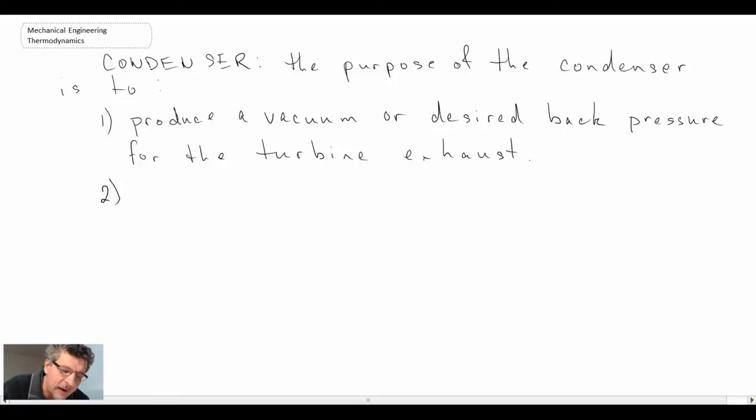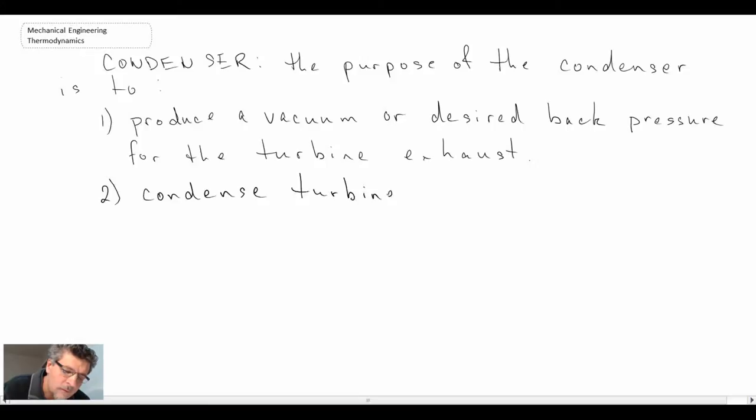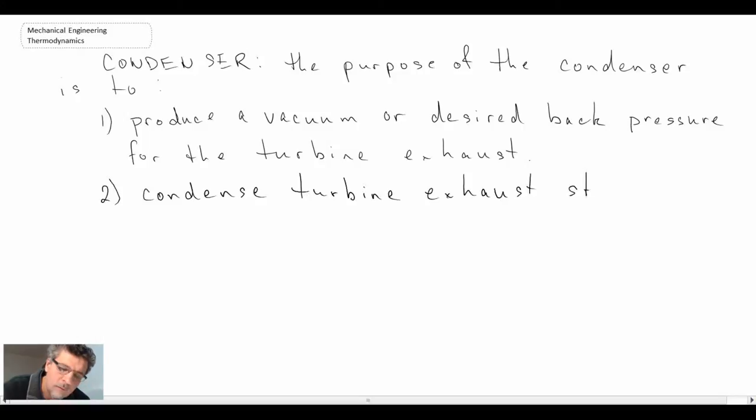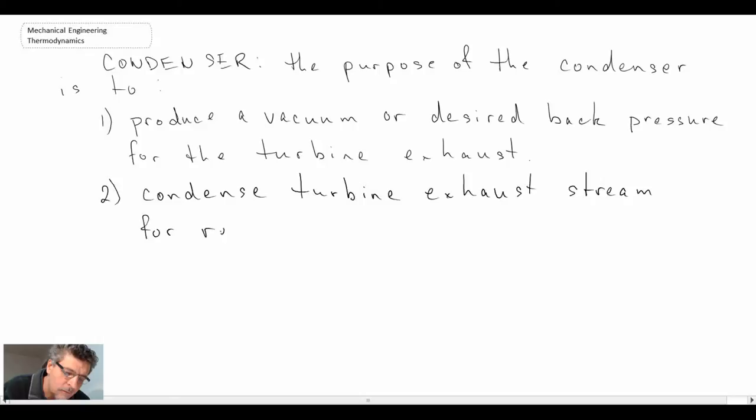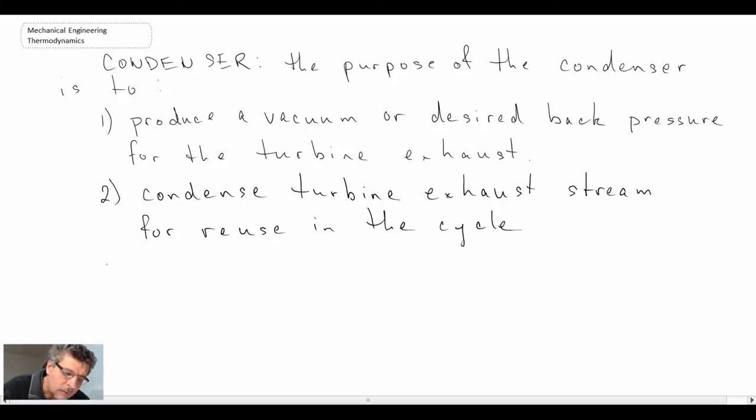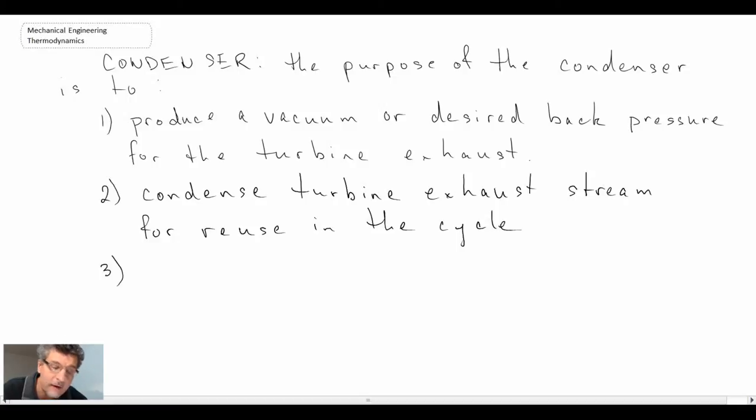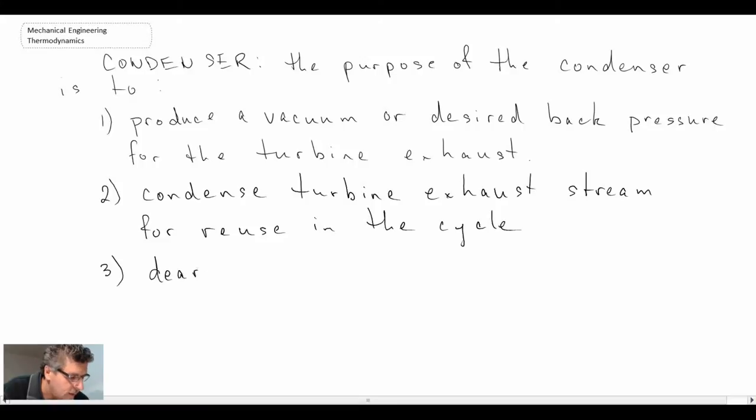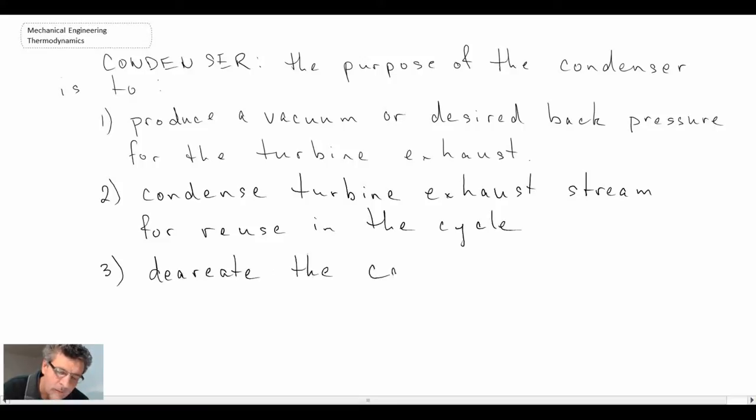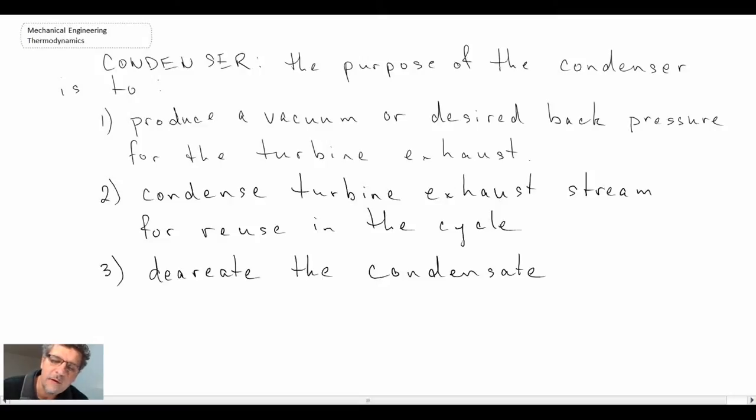So a second purpose. And a third purpose of the condenser is to de-aerate the condensate. So that is to get rid of any of the residual oxygen that might be in the working fluid. So those are three of the main purposes of the condensing unit.